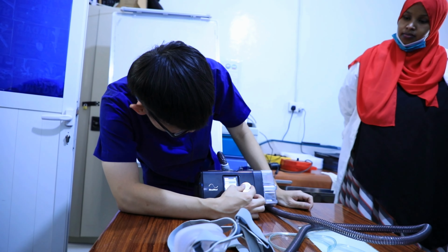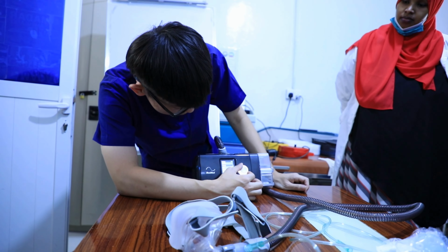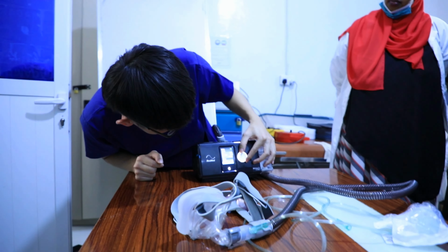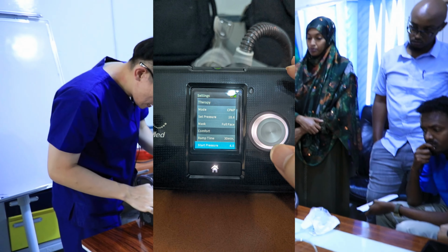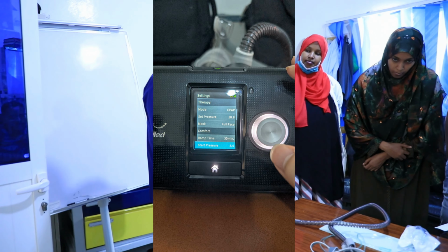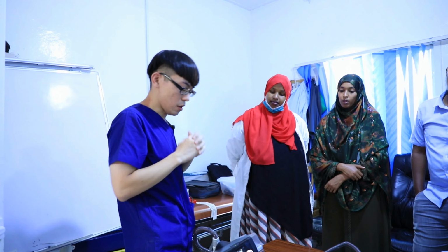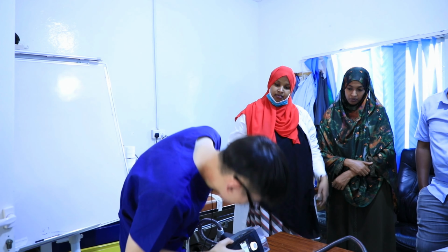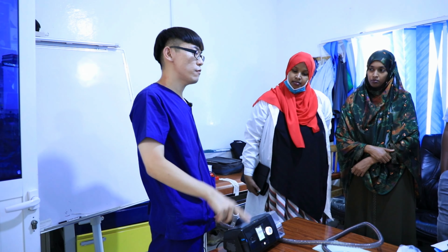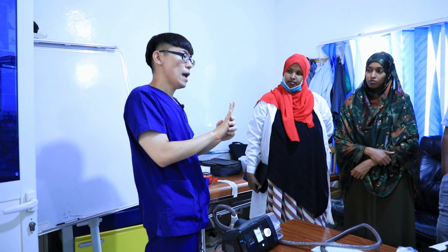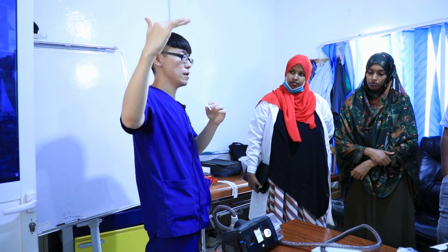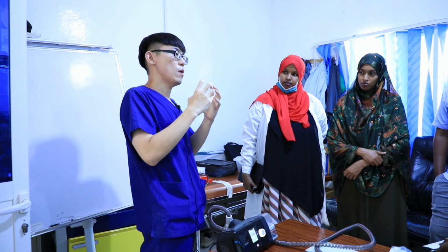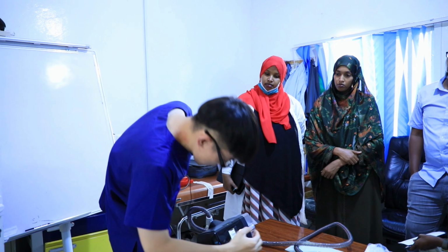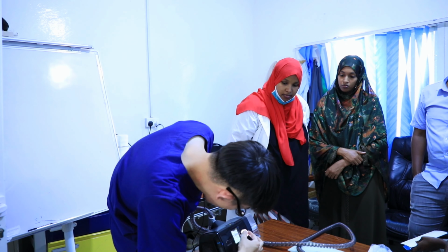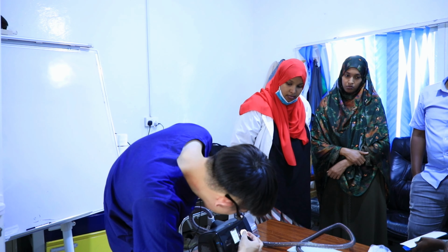And I think the other thing is just auto. We don't need to change it. So auto. Then start pressure: because our CPAP level now is 10, but sometimes the patient cannot tolerate this high pressure, if we set the start pressure around 4, the ventilator will deliver 4 centimeters of water pressure initially, and then gradually increase the pressure to 10. So we do not directly give the patient 10 centimeters of water. It's just for comfort. So maybe you can start from 4, and our setting is just auto. I think that's fine.